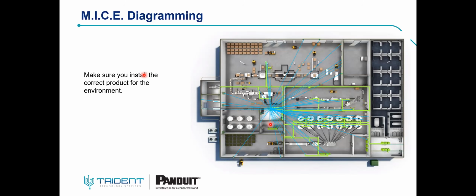When you are going to design, you should not use one cable traversing multiple areas, because it will have high cost, because the cable needs to meet all requirements for all areas. For the green lines, you need to have structured cabling. Structured cabling means that each cable is restricted to a given area. Based on your area, you can structure this cabling and use it based on the environment. So you save cost, not having the same cables in all environment conditions.